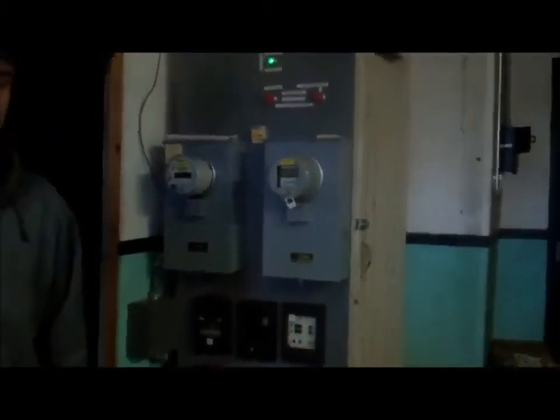And we've got a 48 volt DC backup in there, and because we're over a megawatt, by law we have to have a pole-mounted circuit breaker. It's called a recloser. When you see a square-looking transformer on a telephone pole, it's a recloser. What happens is a branch goes across 2 lines, creates a short, and then it normally either vaporizes whatever caused the short or breaks the line. The recloser will open and then automatically try to reclose every couple seconds for 30 seconds, and then you've got to manually reclose it.